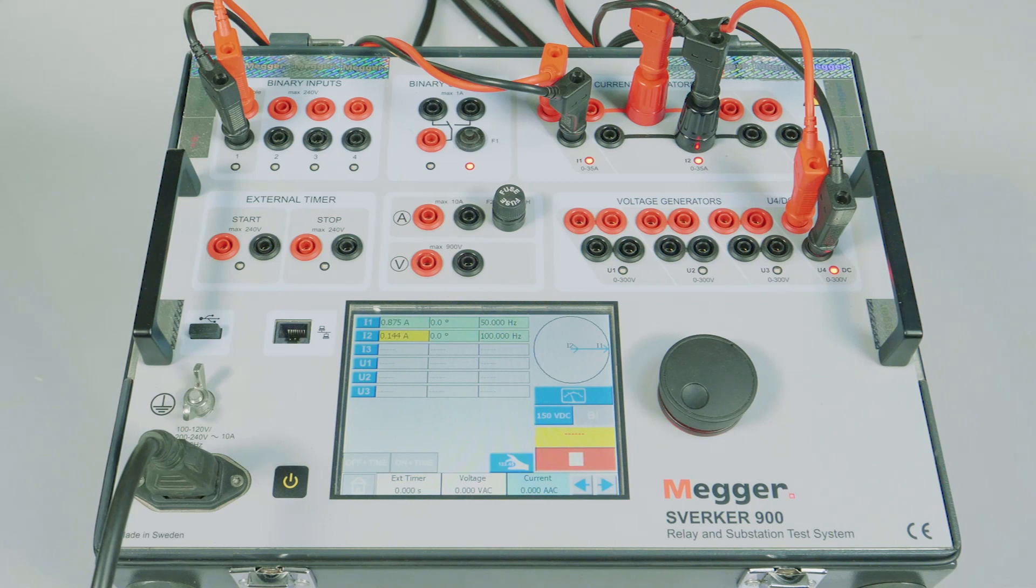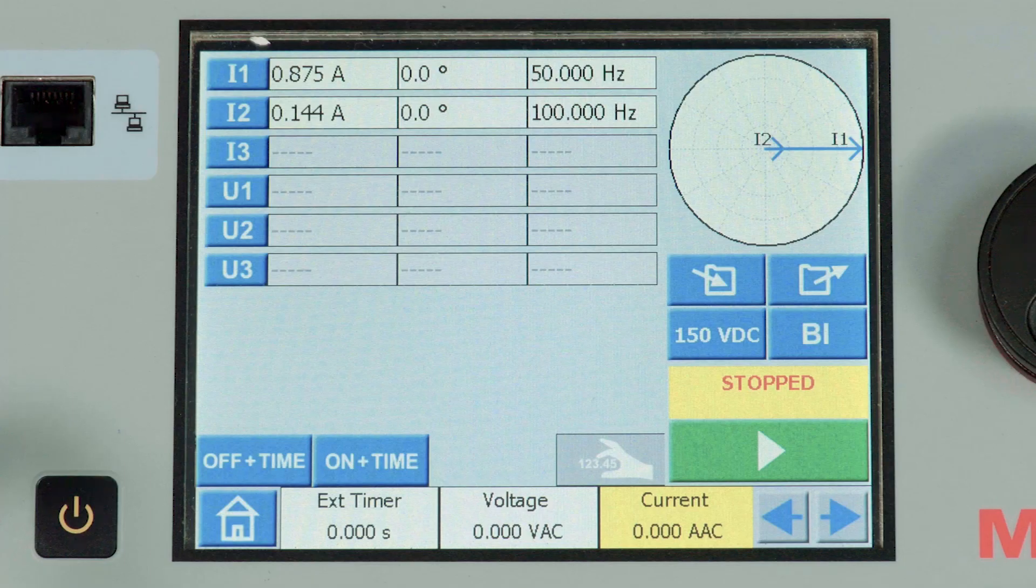This test confirms that the relay is operating when the second harmonic content is less than 15% and blocking when the second harmonic content is more than 15%.